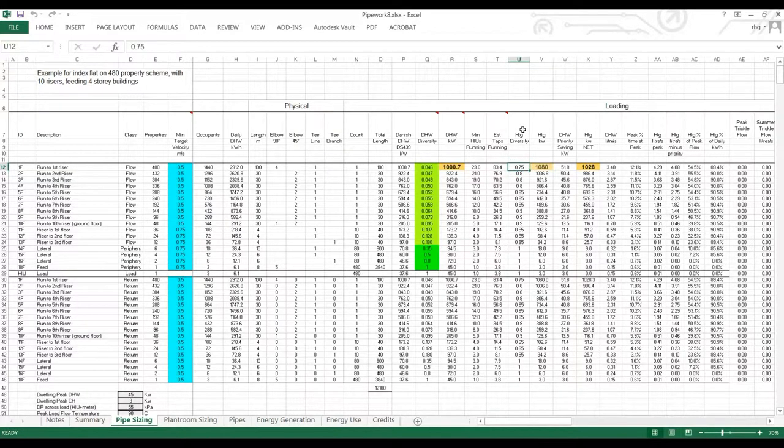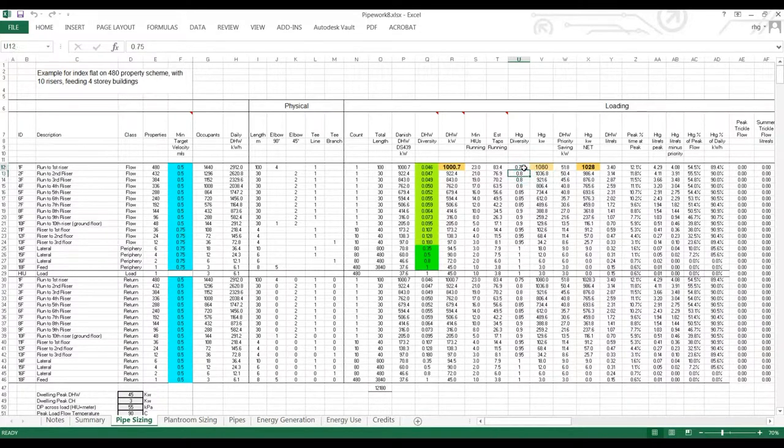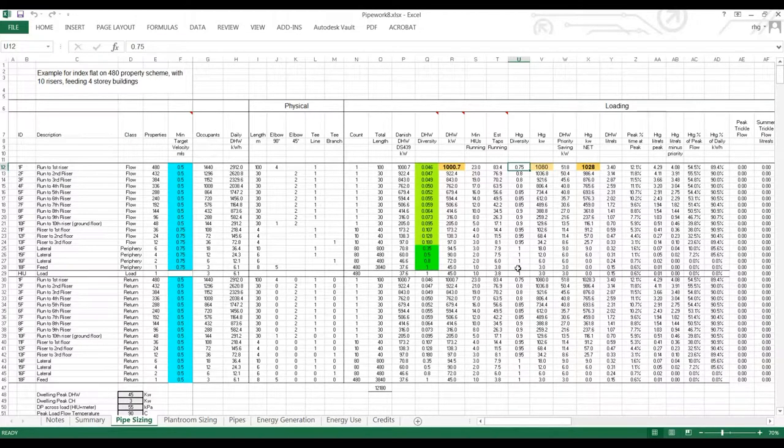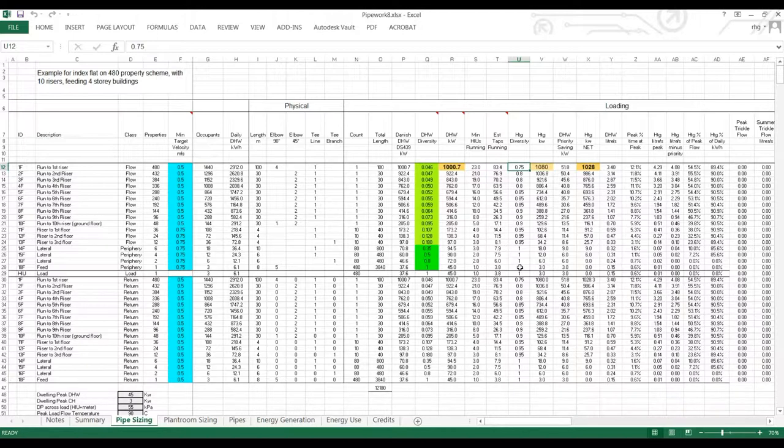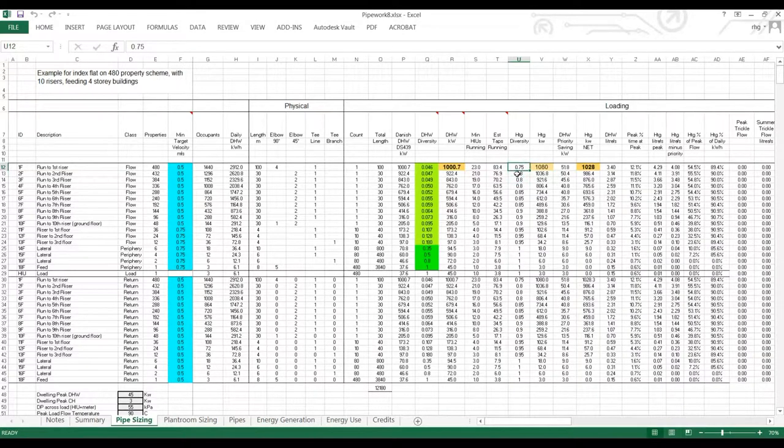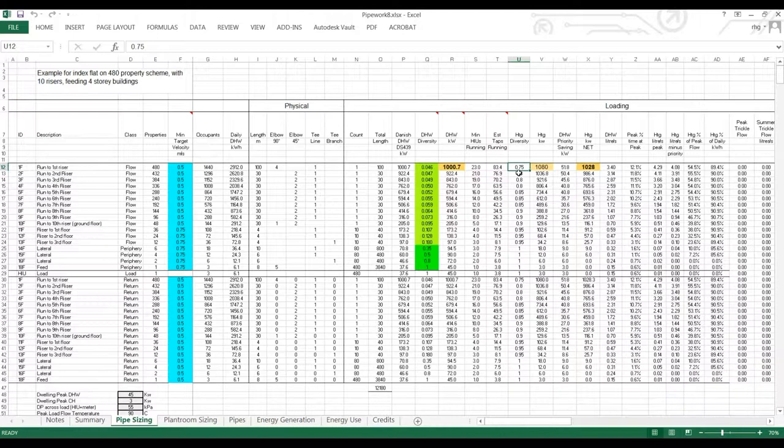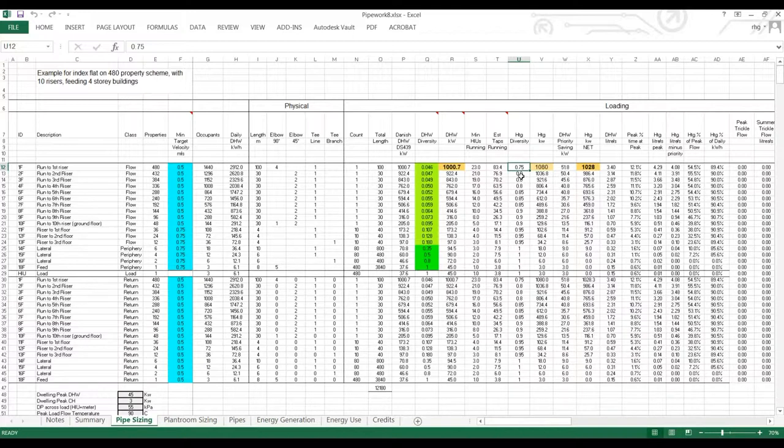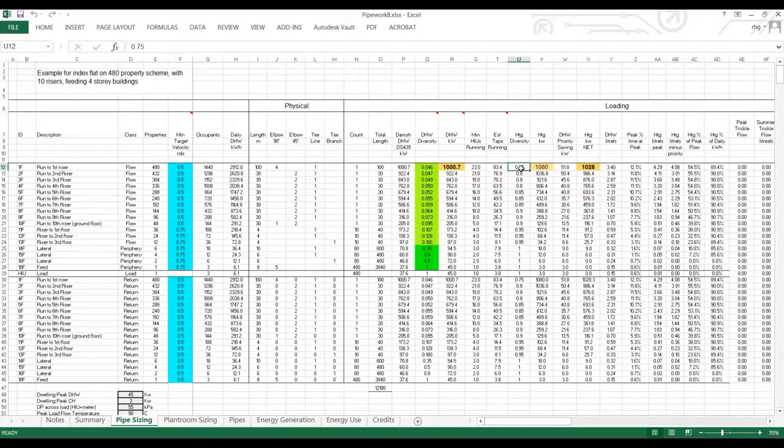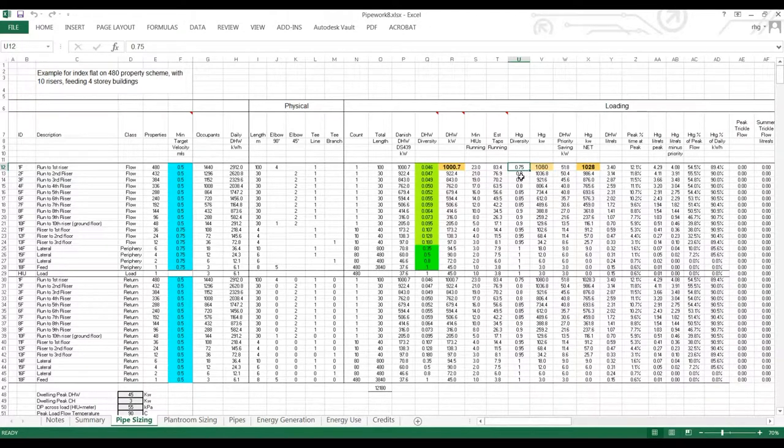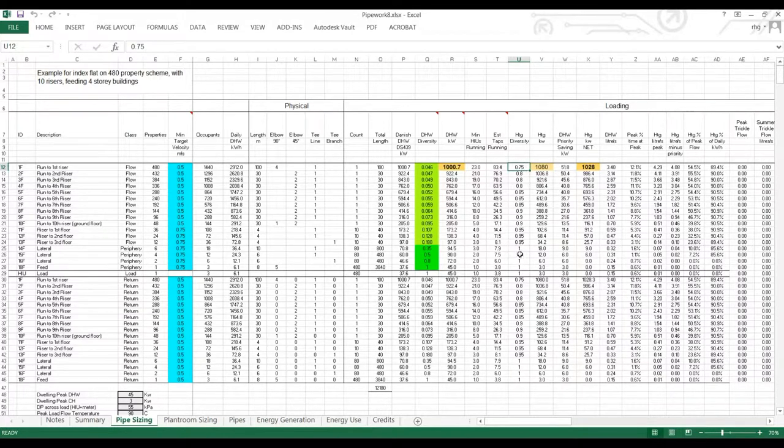The heating diversity. So like the hot water diversity, but this also takes into account a reflection of the difference between the heating output in a single flat, which will generally allow for the adjacent flats to be cold, and the output from a building in general. So when the whole site is at peak load, all ten buildings up to full temperature, very cold outside, the peak load is the sum of the heat losses from the buildings, rather than the sum of the heat losses from the individual dwellings. And this is also reflected in the heating diversity.